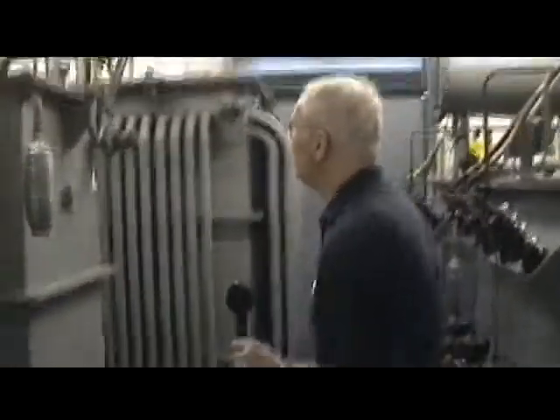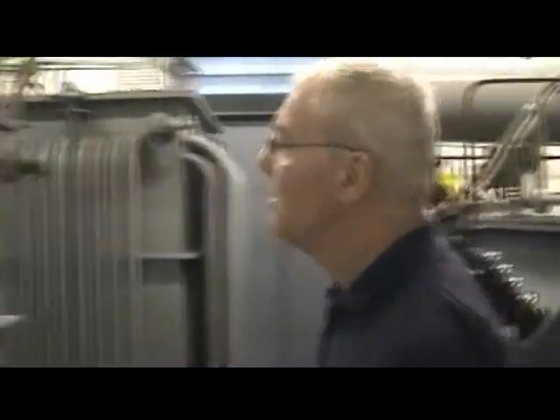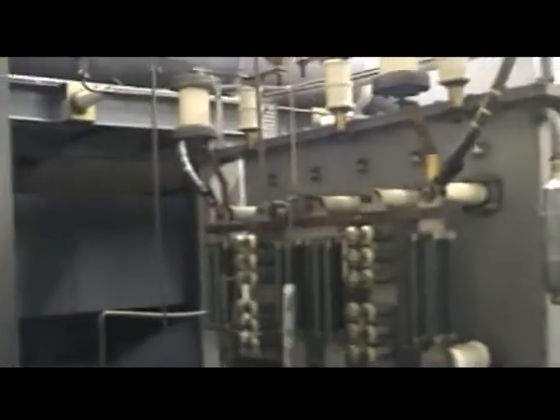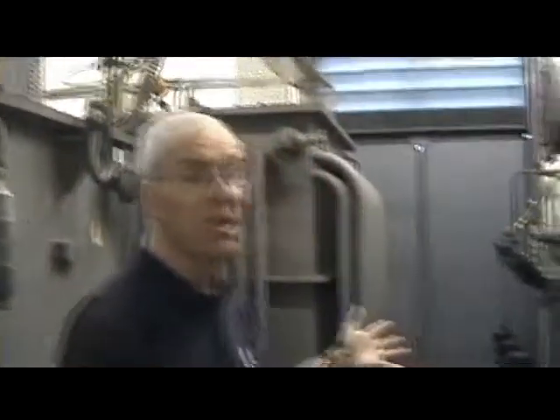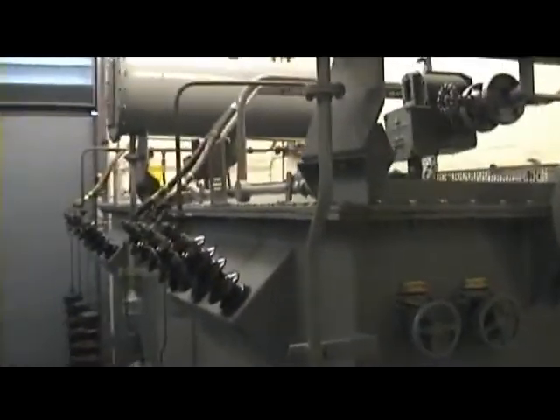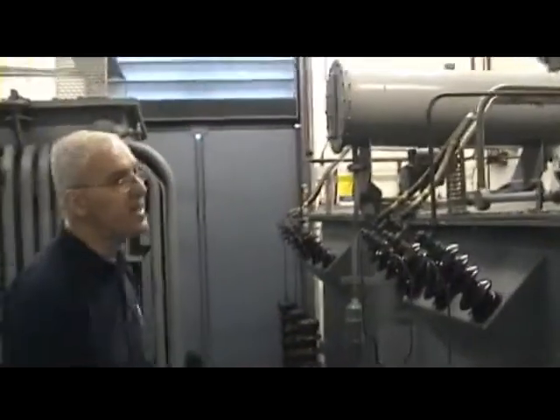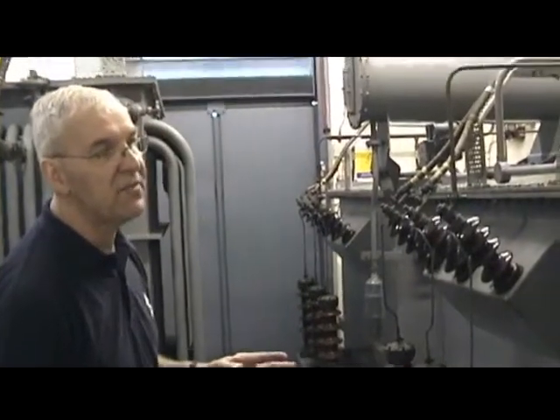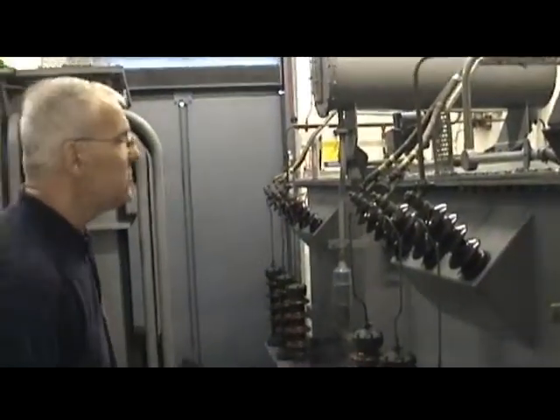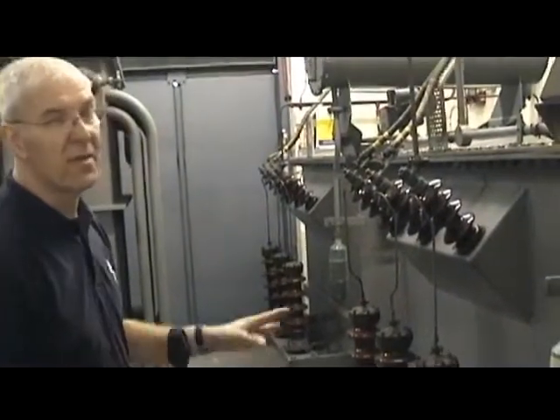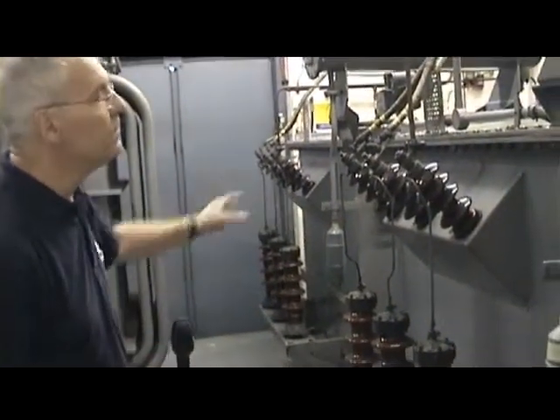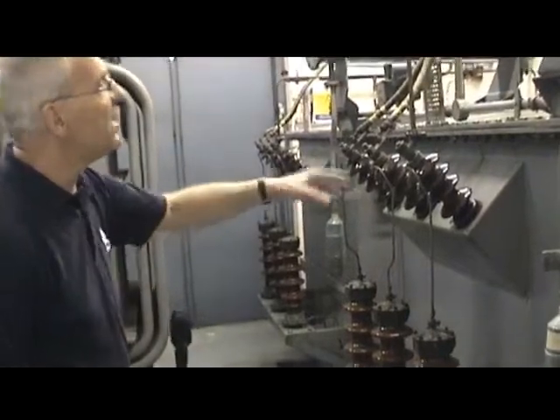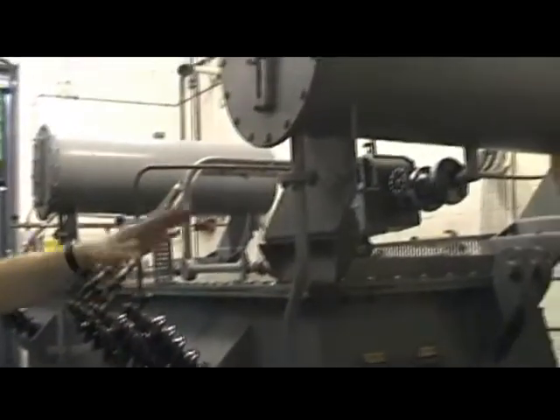I've already got a key here in the door, so we can open the door, go in through, and this is the sort of oily, smelly type area where the transformers live. The mains transformers, actually, because there are two of them, are here. These take 11 kV, 11,000 volts AC from the national grid, and drop it down to about 10,000 or 9,000 volts.